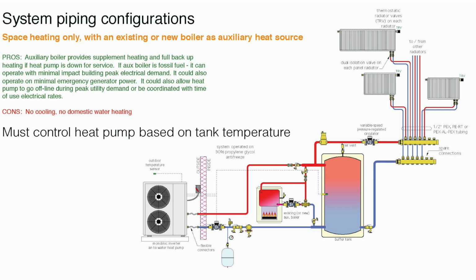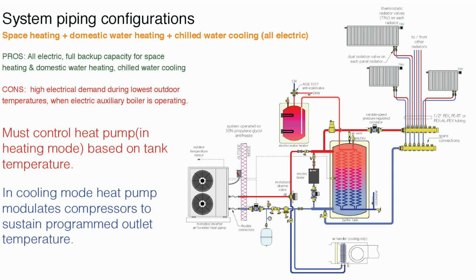So either the boiler or the heat pump can inject heat into that buffer tank, and that tank's actually what we call a three-pipe buffer that could basically allow heat to go directly from the heat source out to the load if they're both operating at the same time. That looks like a pipe, but it's not. It's a vent that's not connected right there. So this is the takeoff right here for the hot water.